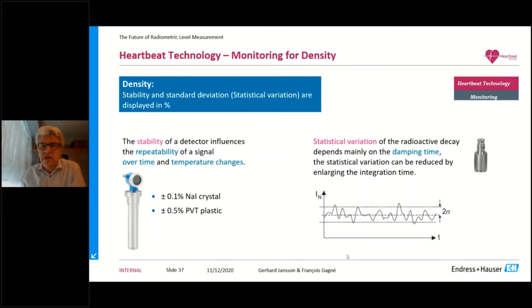So therefore, we're typically talking about a fairly long integration time. Usually by default, we would have 60 seconds damping time on a density application. And usually that is not the problem. There are very few density applications that I know of where you would have a big change in the density in just a few seconds. Usually these are changes that happen over a longer time. So 60 seconds damping time is usually not the problem.